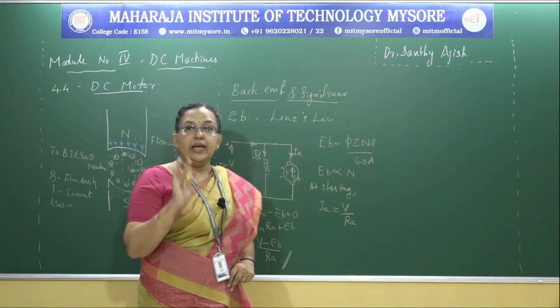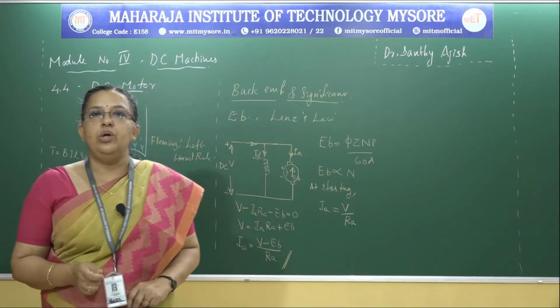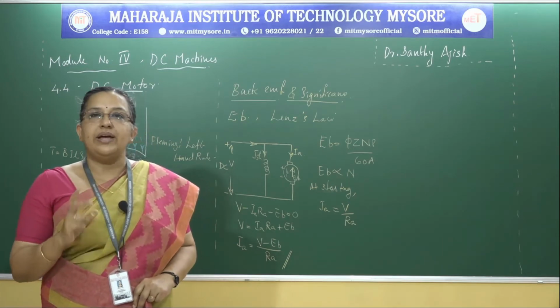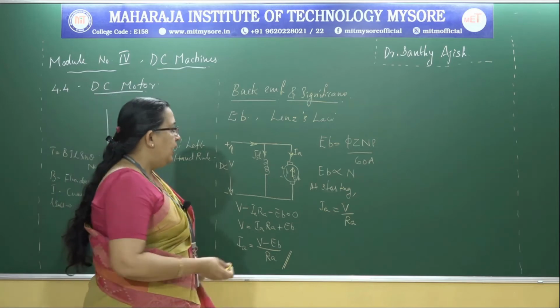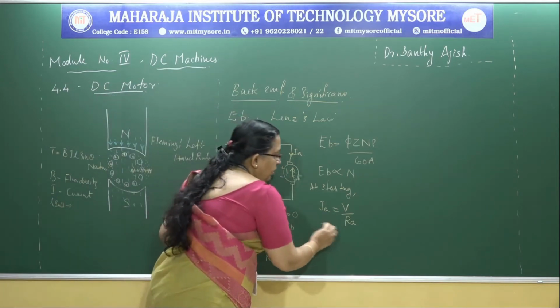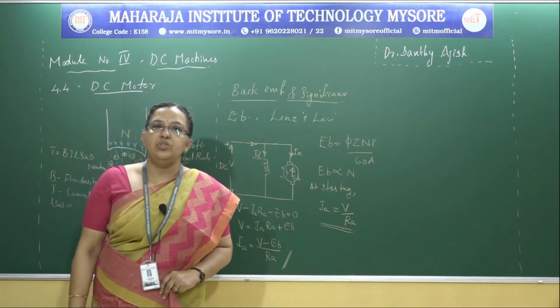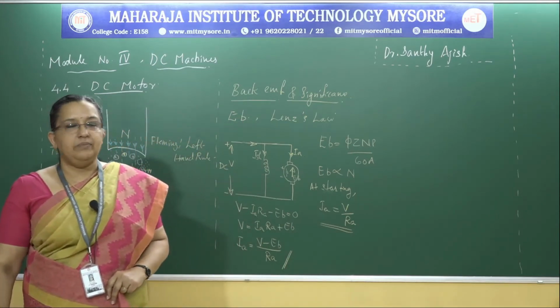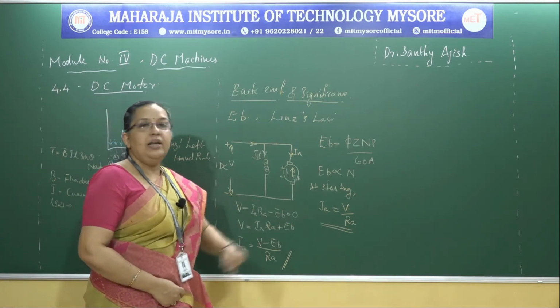Applied voltage is high. So as the RA of the motor is very low, the current produced at starting will be very high, which may be many times more than the maximum rating of the winding. So it may damage even the winding. So this is the current relation.